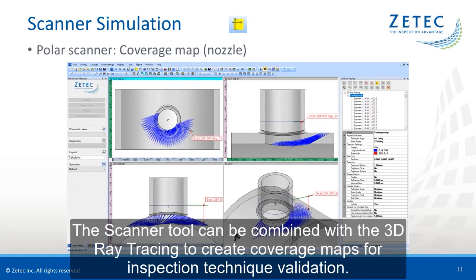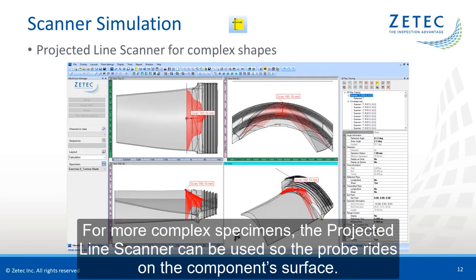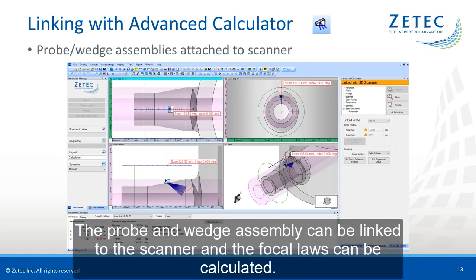The scanner tool can be combined with 3D ray tracing to create coverage maps for inspection technique validation. For more complex specimens, the projected line scanner can be used so the probe rides on the component surface.